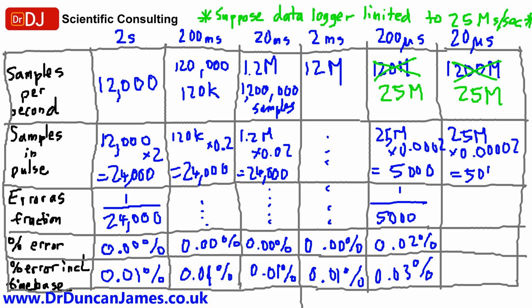That's actually 500. It's not as bad as you might think. Well, it surprises me anyway. You're like, oh, actually, it's still 0.2% accurate. Depends on your application. For a lot of people, that's fine. And let's say that's 0.21%.